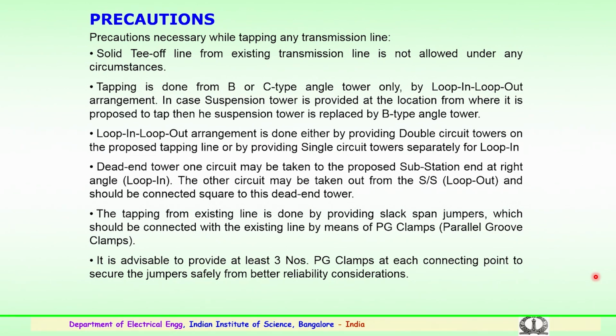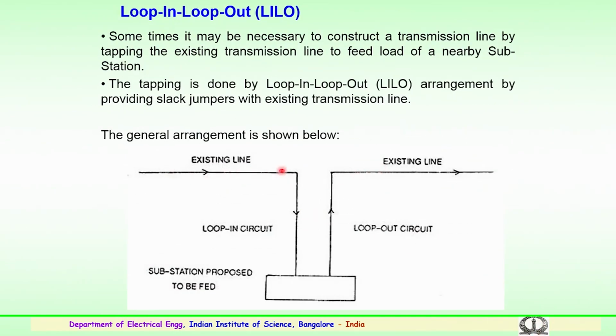Before this is done, the necessary tower arrangement has to be made. Then the loop in loop out arrangement is done either by providing double circuit towers on the proposed line or by providing single circuit towers separately for the loop in. The next point to be considered is the dead end tower. In the case of the dead end tower, one circuit may be taken to the proposed substation or a feeding station at a right angle as a loop in. The other circuit, the loop out, may be taken out from the substation and should be connected square to this dead end tower as shown. So, the one is the loop in circuit, the other is the loop out circuit which is to be taken out from the substation.